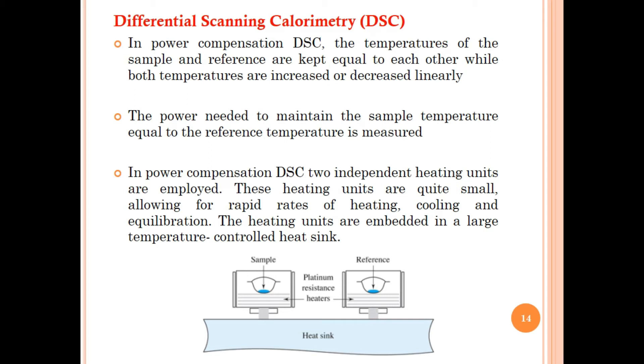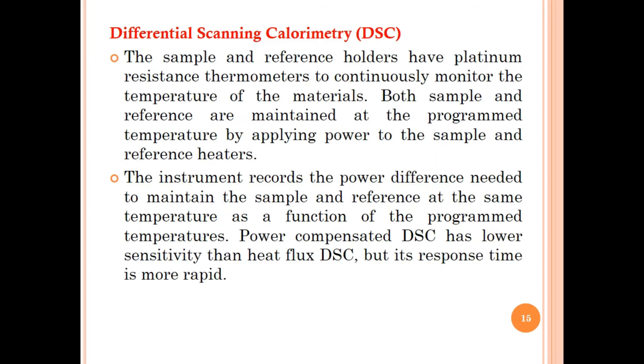The sample and reference holders have platinum resistance thermometers to continuously monitor the temperature of the material. Both sample and reference are maintained at the program temperature by applying power to the sample and reference heaters. The instrument records the power difference needed to maintain the sample and reference at the same temperature as a function of programmed temperature. Power compensated DSC has lower sensitivity than heat flux DSC, but its response time is more rapid.